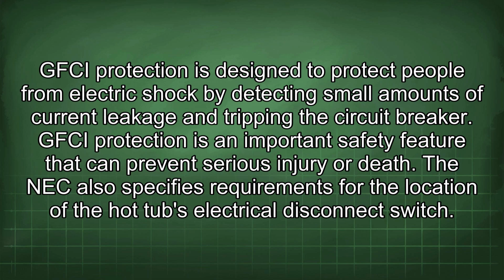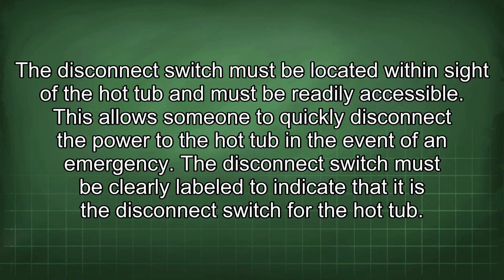The NEC also specifies requirements for the location of the hot tub's electrical disconnect switch. The disconnect switch must be located within sight of the hot tub and must be readily accessible. This allows someone to quickly disconnect the power to the hot tub in the event of an emergency. The disconnect switch must be clearly labeled to indicate that it is the disconnect switch for the hot tub.